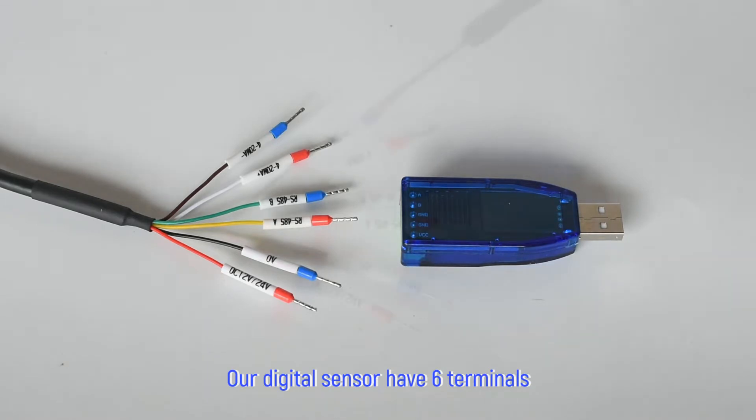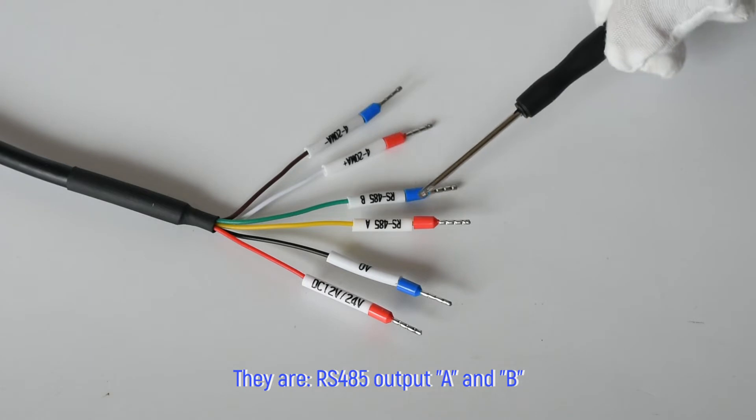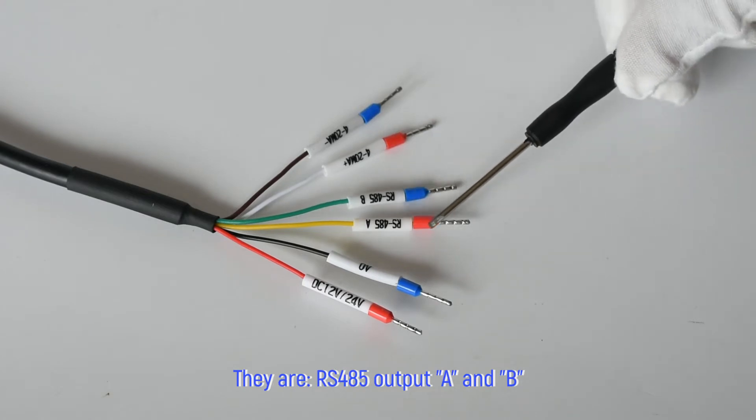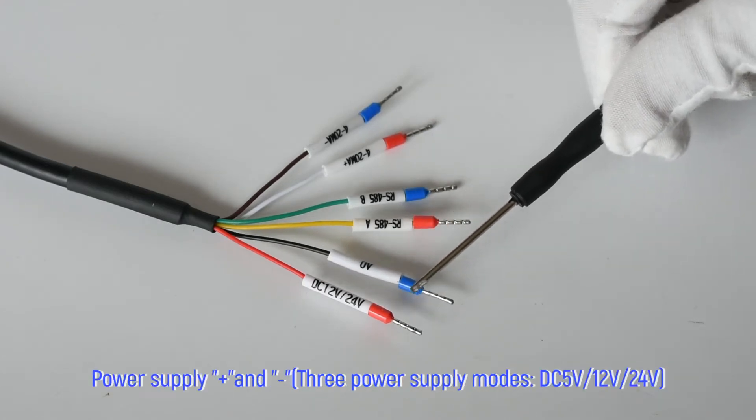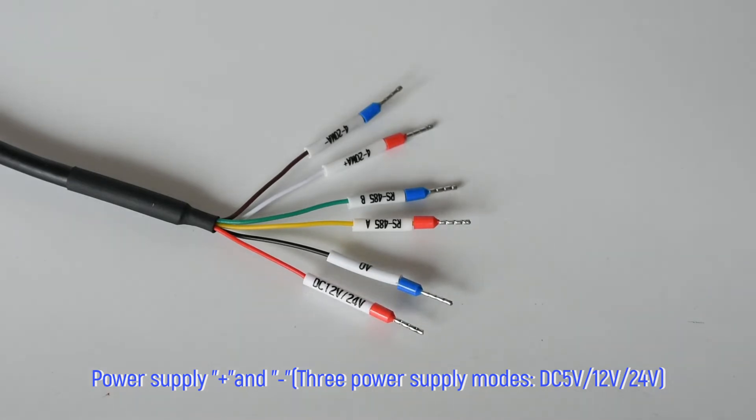Our digital sensor has 6 terminals: 4 to 20 mA output plus and minus, RS485 output A and B, power supply plus and minus. There are 3 power supply modes: DC5V, DC12V, and DC24V.